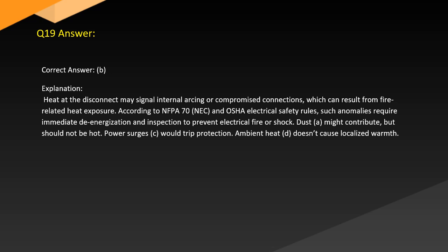Answer. Correct answer: B. Explanation. Heat at the disconnect may signal internal arcing or compromised connections, which can result from fire-related heat exposure. According to NFPA 70 NEC and OSHA electrical safety rules, such anomalies require immediate de-energization and inspection to prevent electrical fire or shock. Dust, A, might contribute but should not be hot. Power surges, C, would trip protection. Ambient heat, D, doesn't cause localized warmth.